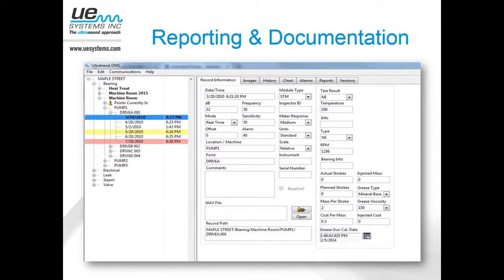Just a couple examples, and I'm winding it down here since we're getting close to the time. Reporting and documentation: the software you can use with these ultrasonic detectors is really user-friendly and easy. You can set up routes, do monthly trending, and see here we're trending this over time. Here it hit a low alarm point, kept going, and here it hit a high alarm.